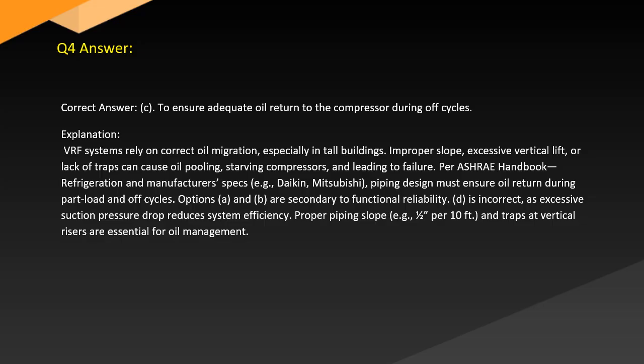Explanation: VRF systems rely on correct oil migration, especially in tall buildings. Improper slope, excessive vertical lift, or lack of traps can cause oil pooling, starving compressors and leading to failure. Per the ASHRAE Handbook, Refrigeration, and manufacturer specs, e.g., Daikin, Mitsubishi, piping design must ensure oil return during part load and off cycles.